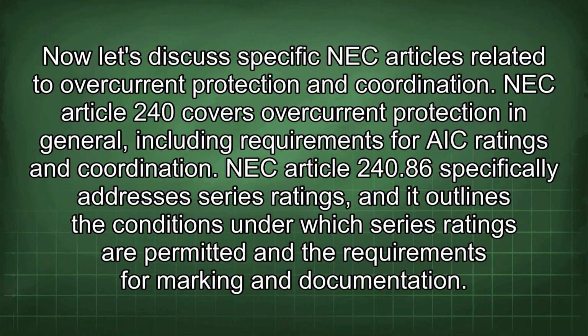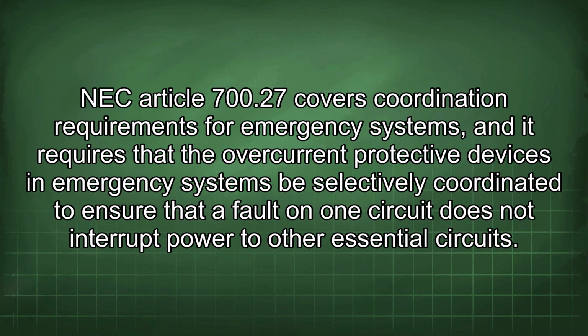Now let's discuss specific NEC articles related to overcurrent protection and coordination. NEC Article 240 covers overcurrent protection in general, including requirements for AIC ratings and coordination. NEC Article 240.86 specifically addresses series ratings, and it outlines the conditions under which series ratings are permitted and the requirements for marking and documentation.